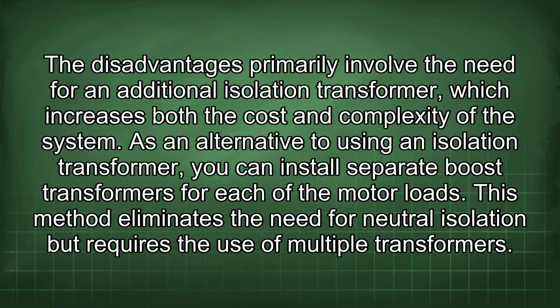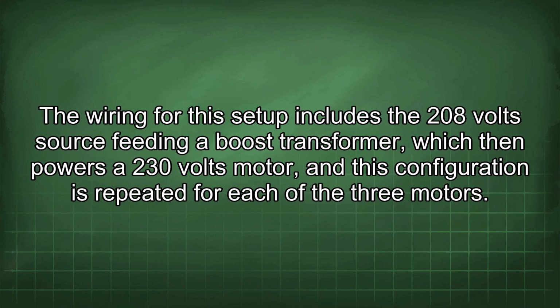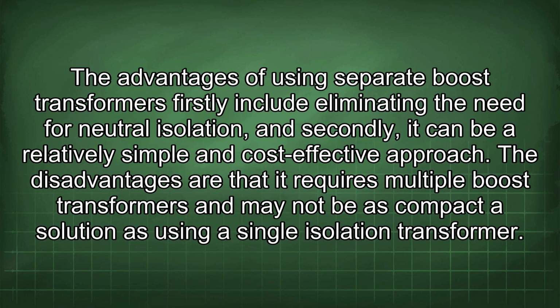system. As an alternative to using an isolation transformer, you can install separate boost transformers for each of the motor loads. This method eliminates the need for neutral isolation, but requires the use of multiple transformers. The wiring for this setup includes the 208 volt source feeding a boost transformer, which then powers a 230 volts motor, and this configuration is repeated for each of the three motors. The advantages of using separate boost transformers firstly include eliminating the need for neutral isolation, and secondly, it can be a relatively simple and cost-effective approach.